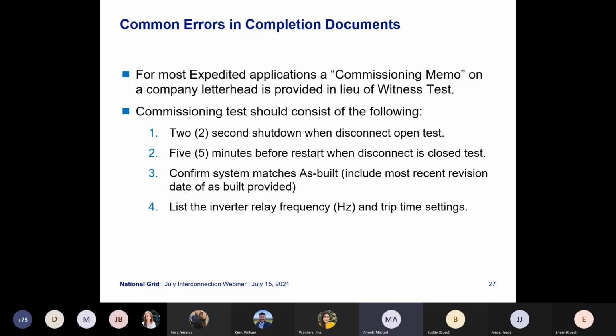Some of the common errors that we see in completion documents and commissioning memos is that they come in missing some information. Instead of a witness test, this commissioning memo should have a 2-second shutdown when the disconnect's open, 5 minutes before restart when the disconnect is closed, and confirm that the system matches the as-built, also with signature and date.